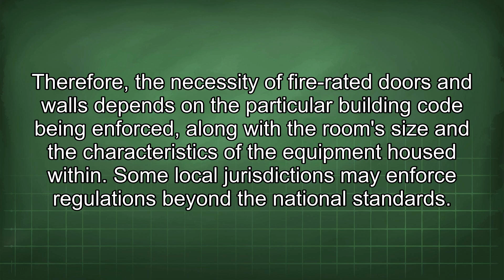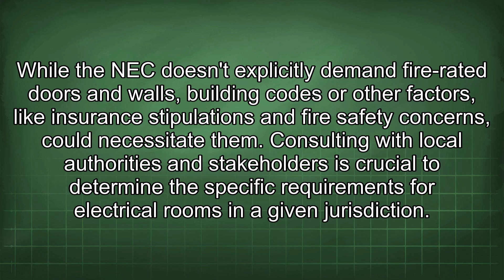Insurance companies could mandate fire-rated doors and walls for electrical rooms to mitigate liability risks in the event of a fire. Fire-rated doors and walls act as barriers, slowing the spread of fire and safeguarding the equipment inside the electrical room. While the NEC doesn't explicitly demand fire-rated doors and walls, building codes or other factors, like insurance stipulations and fire safety concerns, could necessitate them. Consulting with local authorities and stakeholders is crucial to determine the specific requirements for electrical rooms in a given jurisdiction.